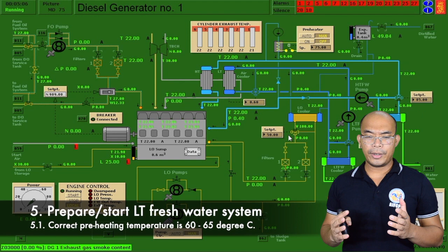Now we will set the preheating temperature to around 60 to 65 degrees centigrade. Turn it on, then connect to auto, meaning once it reaches the 60 to 65 set point, it will turn off automatically to maintain the temperature of the diesel generator at around 65.